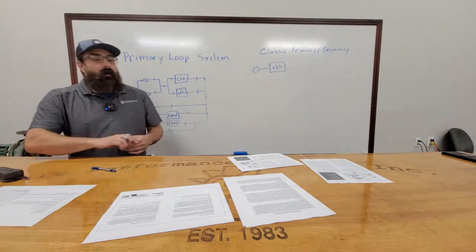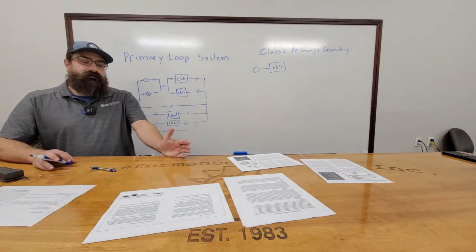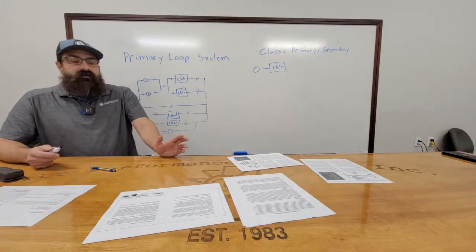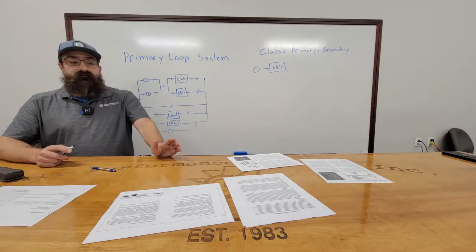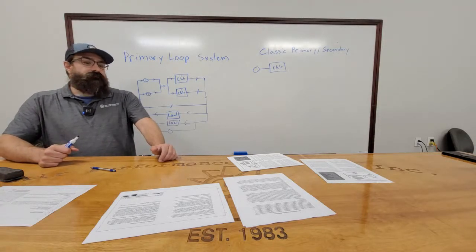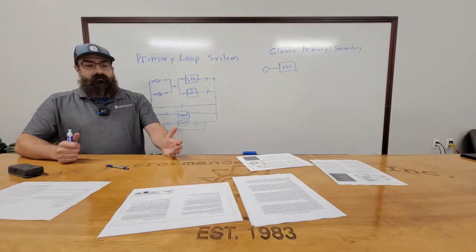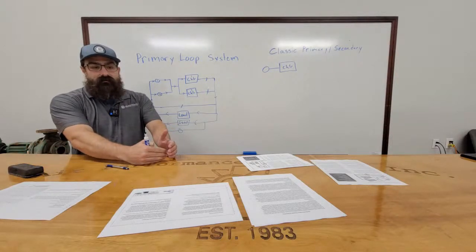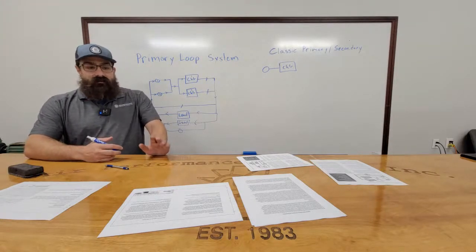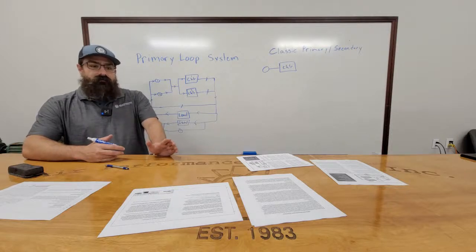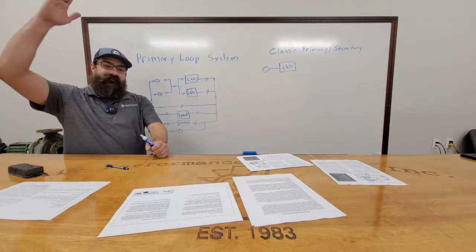It's called a water balance. So a TAB contractor can do a water balance on the system and actually read flows. We have a couple buildings. Most buildings that are primary secondary are going to have flow meters, period. Because especially if it's a variable volume system, like we have a few buildings, one very prestigious customer who I won't name. They have a flow meter on each chiller. So I modulate the VFD based on that flow meter. Then typically it's been set either at the pump with a circuit setter valve or at the chiller with some kind of circuit setter. But sometimes they're just a freaking butterfly valve that's cocked at 45 degrees.